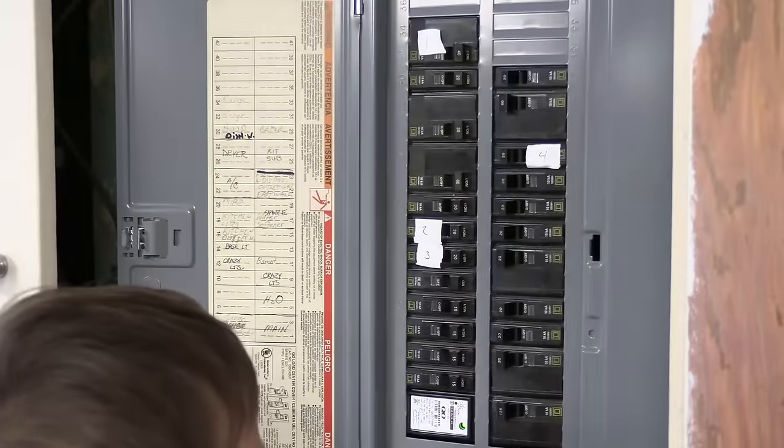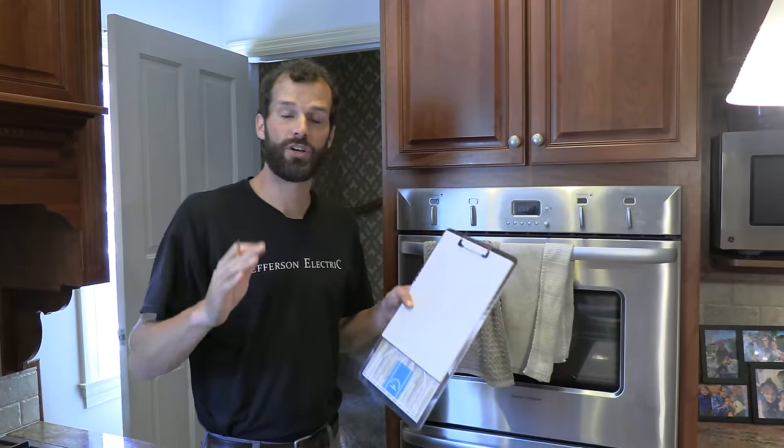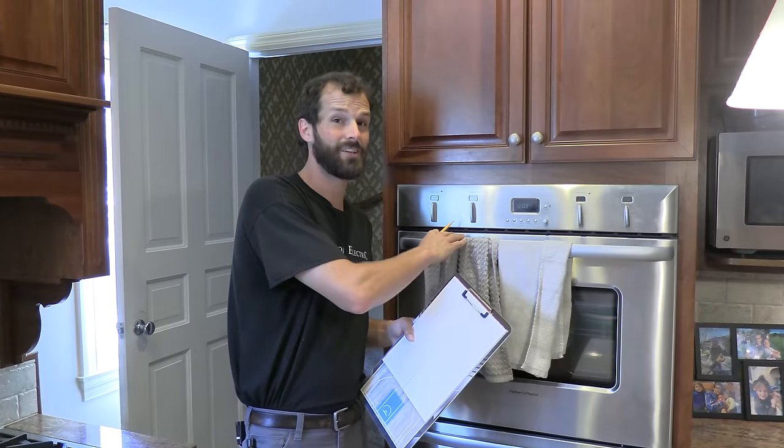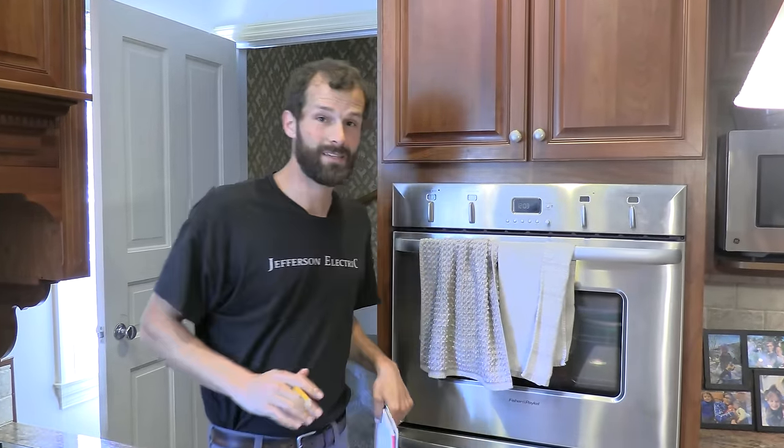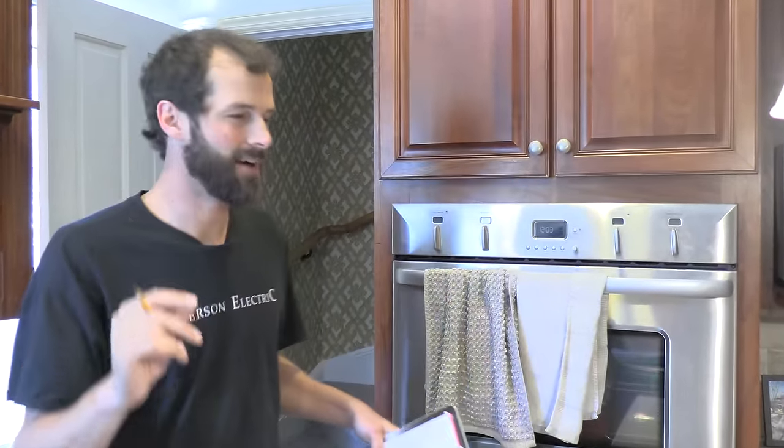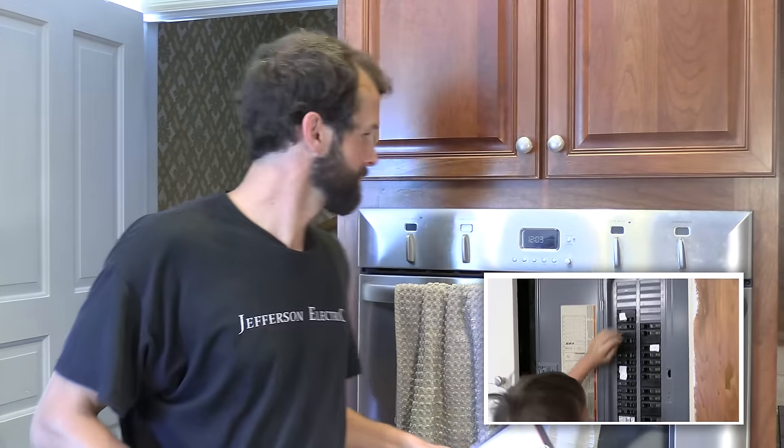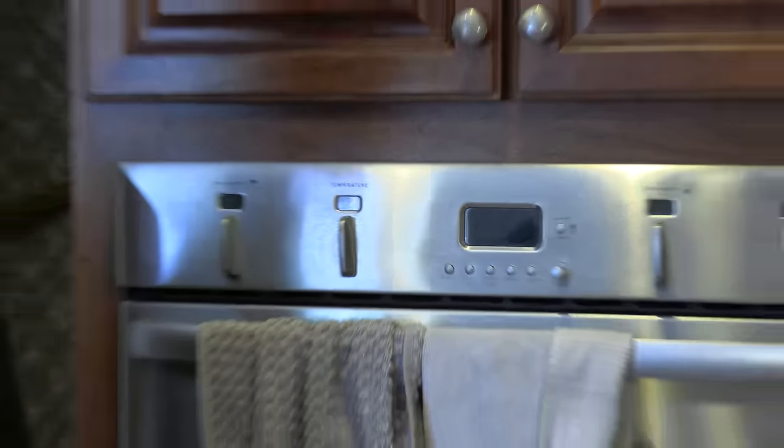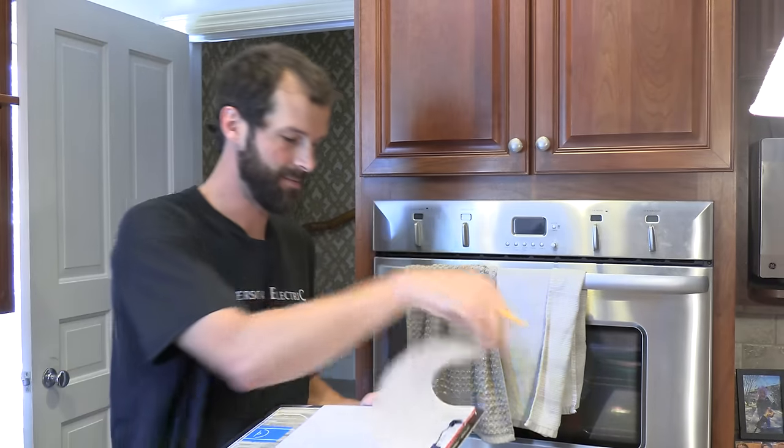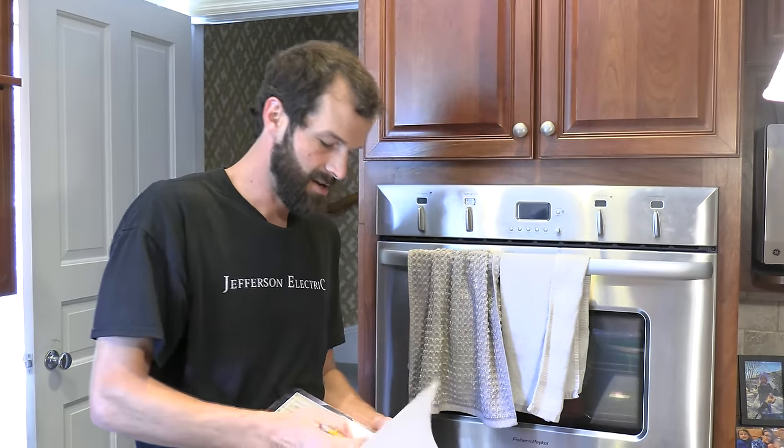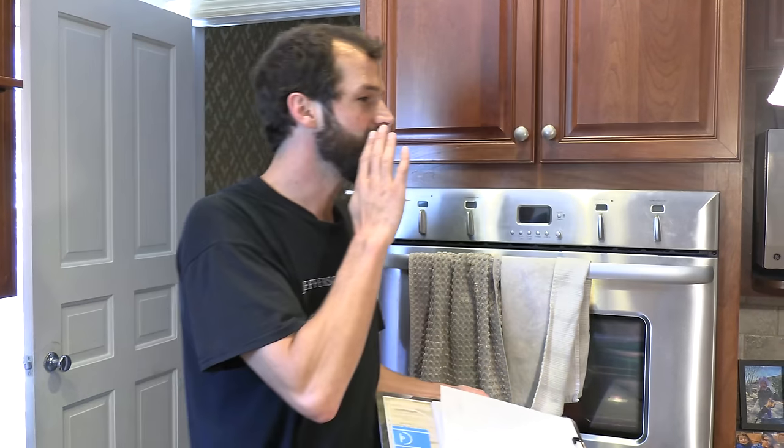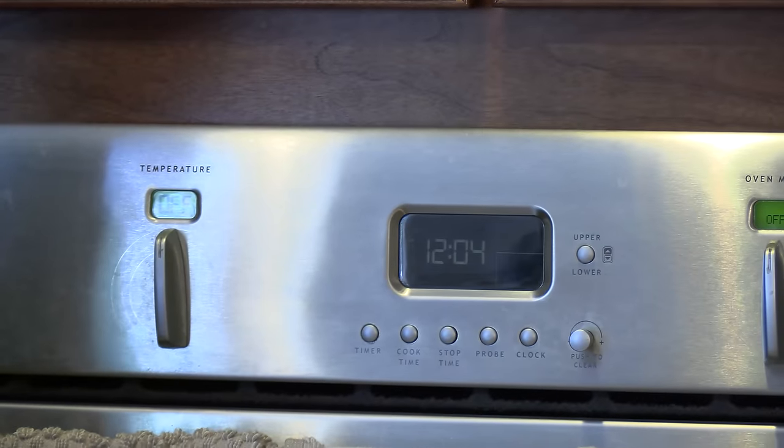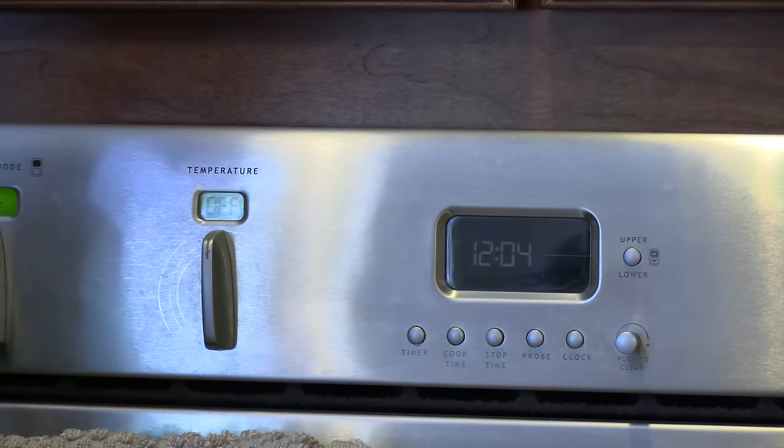Let's head upstairs. Okay. Now we're upstairs in the kitchen. And that first breaker Titus is going to flip, we think it's the oven. And a large breaker like that is for a dedicated appliance. This is an electric oven. So it's got upper and lower elements. And that two pole 40 amp breaker would be just right. All right. Titus, flip breaker number one. Boom. That's it. All right. So I'm going to put a check mark by the confirmed items. I'm going to transition from suspected to confirmed. Turn it on, Titus. Boom. All right. Number two. Go ahead, buddy. Ooh, kitchen lights. Confirmed. Check mark. Turn number two back on, buddy.